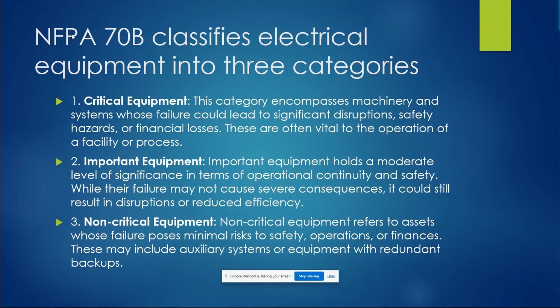On conditions 1, 2, and 3, look at this slide to see what it's evaluating. You'll notice one key factor: nothing ever exceeds 60 months. 5 years is the maximum you can go without an interval for a maintenance inspection. So if you're keeping notes or tracking that, make sure you keep that note. This includes your motor control centers, circuit breakers, switchboards, panel boards, bus ducts, busways, and other big pieces of equipment. They should be inspected at minimum every 5 years.